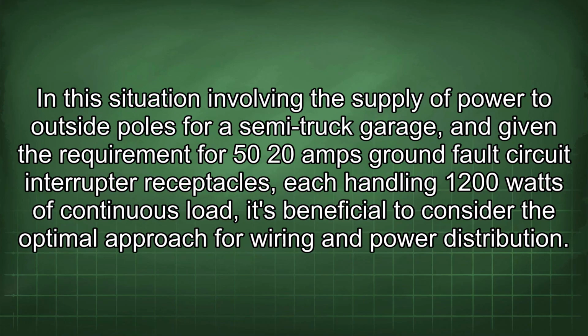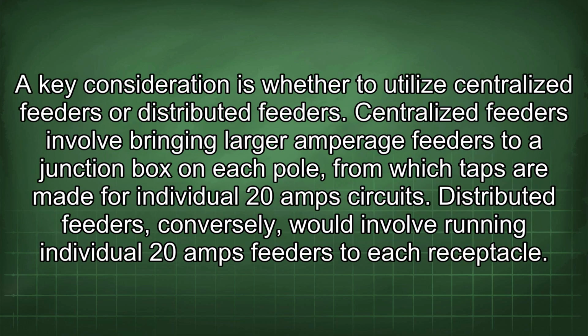In this situation involving the supply of power to outside poles for a semi-truck garage, and given the requirement for 50 20-amp ground fault circuit interrupter receptacles, each handling 1200 watts of continuous load, it's beneficial to consider the optimal approach for wiring and power distribution. A key consideration is whether to utilize centralized feeders or distributed feeders.